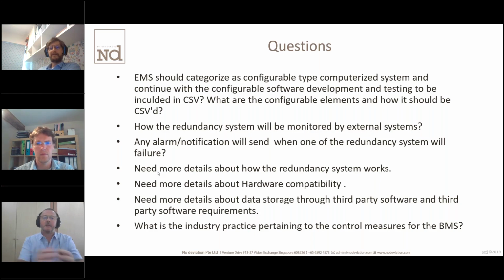Well, I suppose that depends on what you mean by control measures. If you're talking about compliance and qualification control, the BMS doesn't have it—this is specifically why we're talking about EMS systems today, so you can avoid having those extra control measures within the BMS. If you're talking about control parameters like temperature and humidity, that's entirely dependent on the process being served. If it's an office environment, you're controlling around 23-24 degrees and 50-60% humidity. If it's a clean room, you might be down at 18 degrees and 30% humidity, depending on product requirements. So if you can clarify the question a bit more, we can give a more specific response.